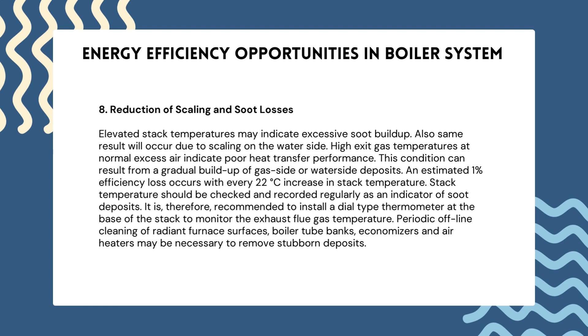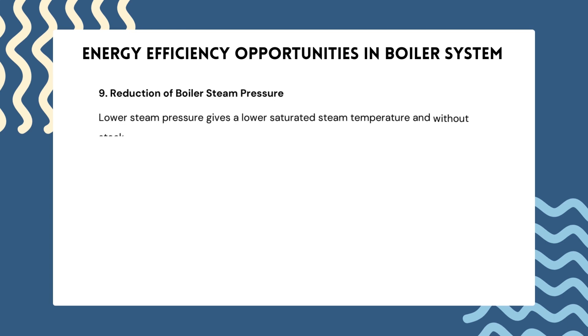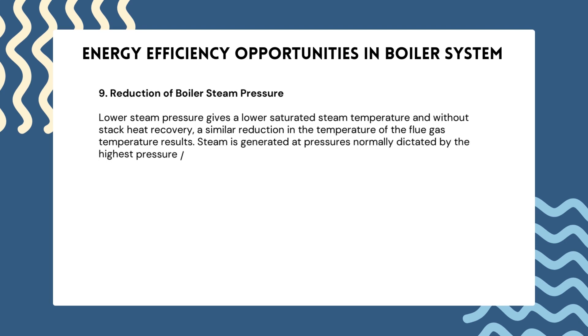An estimated 1 percent efficiency loss occurs with every 22°C increase in stack temperature. Stack temperature should be checked regularly as an indicator of soot deposits. When the flue gas temperature rises 20°C above that of a newly cleaned boiler, it is time to remove soot deposits. It is recommended to install a dial thermometer at the base of the stack to monitor exhaust flue gas temperature. An estimated 3 mm of soot can cause a 2.5 percent increase in fuel consumption. Ninth, reduction of boiler steam pressure is an effective means of reducing fuel consumption by as much as 1 to 2 percent.